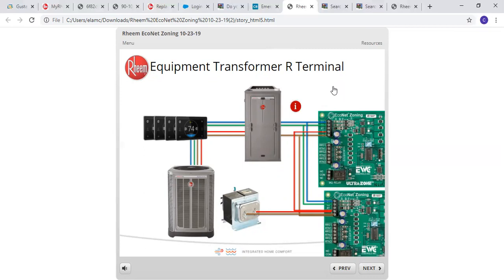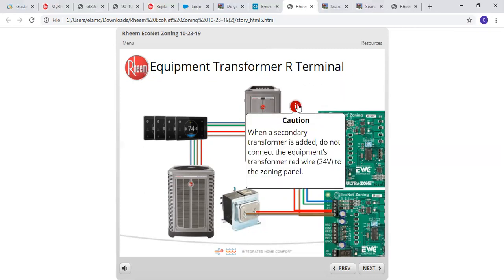This is the equipment transformer R terminal. Caution: when a secondary transformer is added, do not connect the equipment's transformer red wire, 24 volts, to the zoning panel.